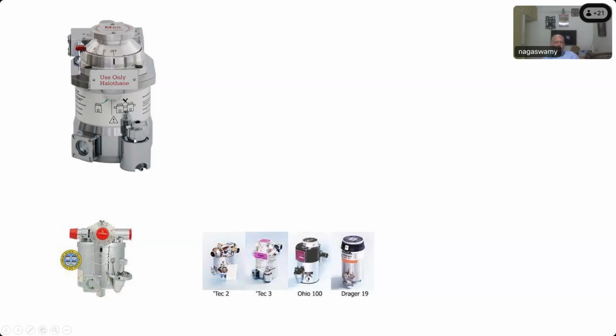This is a cap for the filling port. No. So in this machine, what you have to do is unscrew it by rotating it anti-clockwise, and then you can remove the whole thing. This cap you can remove completely, and you will find the hole there. You just pour the halothane from the bottle into that, and you can see the level rising here. And once you finish filling it up to the full mark, you can screw back this cap.